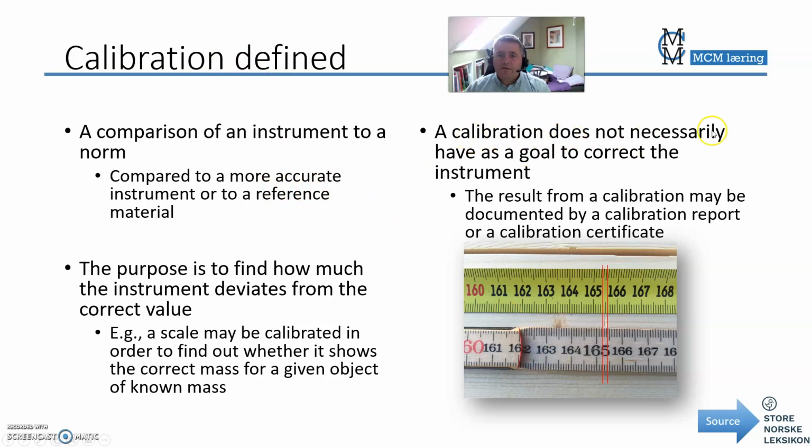The calibration doesn't necessarily have as a goal to correct the instrument, but the result from a calibration should be that you document the accuracy by a calibration report or a calibration certificate.